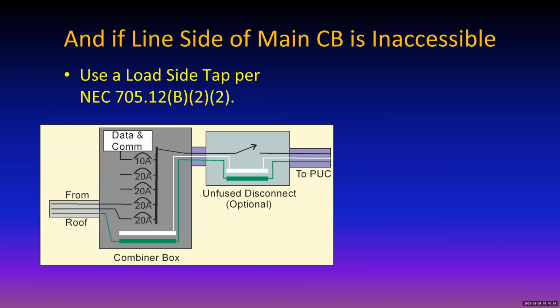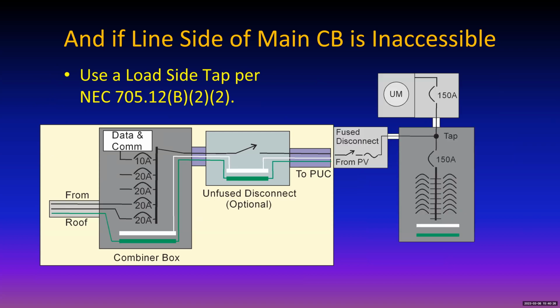Well, you might do something like this. You use a load side tap. What that means is you're going to add an extra 150 amp circuit breaker to the main distribution panel, and you've got your 150 amp main disconnect up there, and we tap right in between the two of those. All right, and what does that do for you? Well, the most current that you can go down into that bottom panel is 150 amps. That's protected by that lower breaker. The most current you can get from the utility is 150 amps.